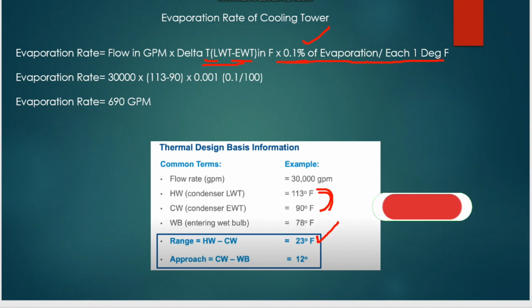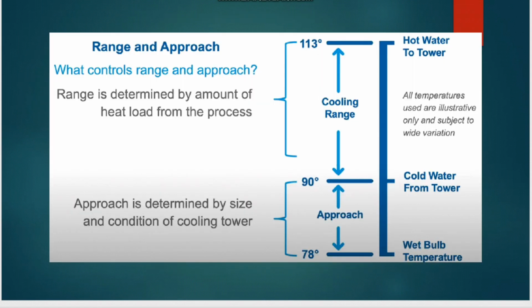So it is 30,000 GPM times the temperature difference, 113 minus 90, times 0.1 by 100, which is 0.001. You have to multiply with the temperature difference in Fahrenheit. So the evaporation rate is equal to 690 GPM. This is the value: this much water, in gallons per minute, is evaporated in the cooling tower.